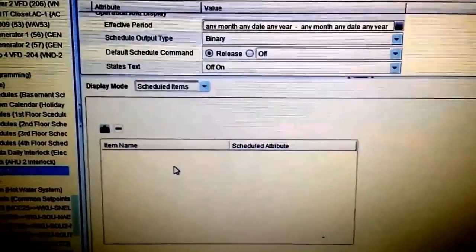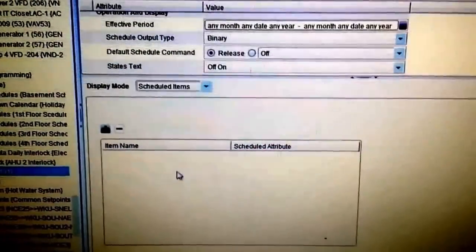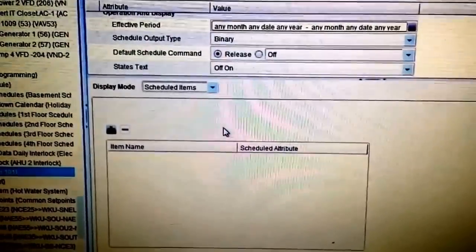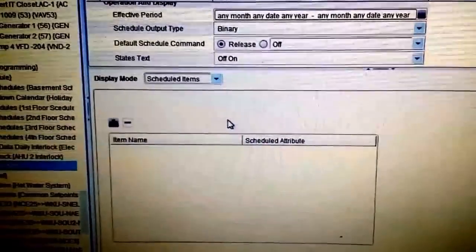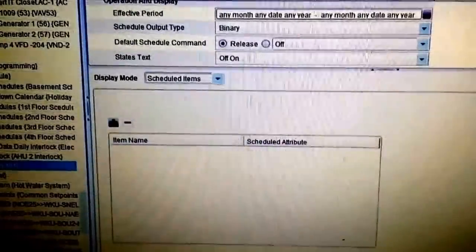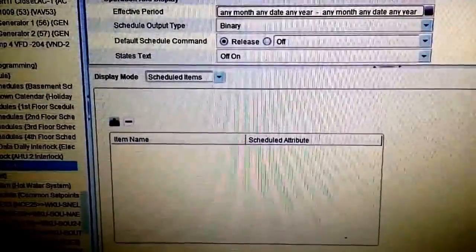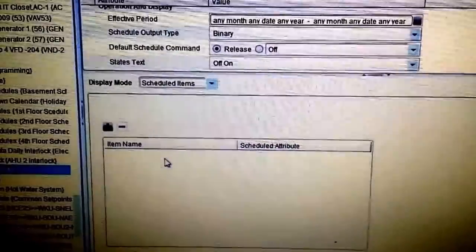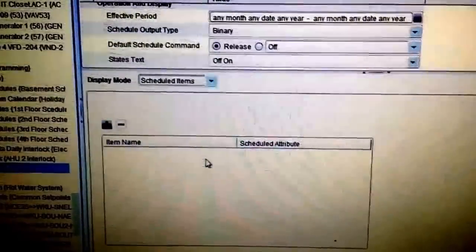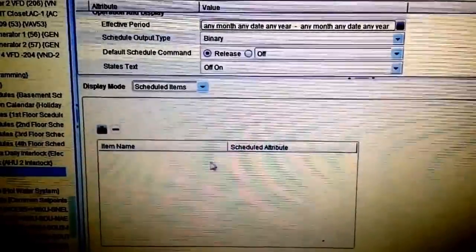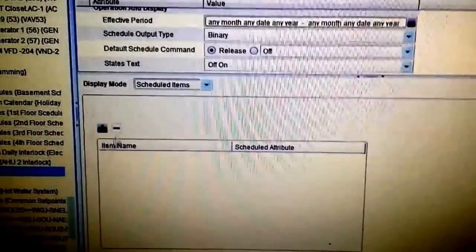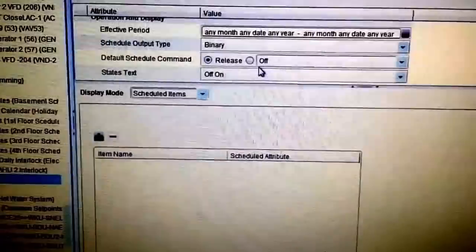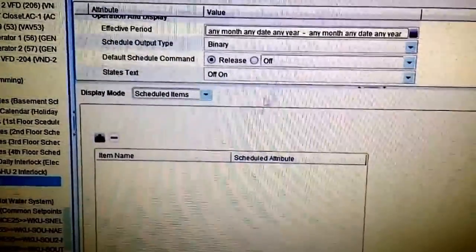You cannot have, for example, an air handler that runs off of an older type of software, like an N2, tied in with the same schedule that you are controlling a BACnet device with. Those values can often go opposite. The way a controller sees a value can often be different from one to the other. And the schedule will look at the top item as the key item, and it will set up a lot of these configurations for you.